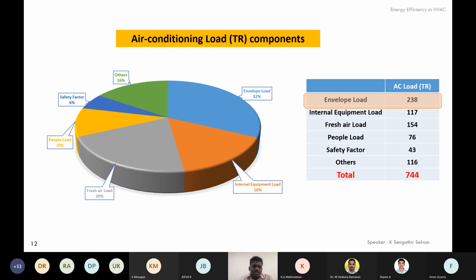Now the internal equipment actually constitutes a very small percentage compared to other loads. The computers and printers and all are very negligible in any commercial building. Of course, in a thermal plant, the heat dissipation from the electrical panels is very low, but the heat dissipation from the VFD drives and other server or other critical equipment will be a little bit high actually. But again, the people load is only 10%, and the fresh air load you can see, Chennai being a humid climate, the fresh air load is actually high. But the same fresh air load will be around 10% only if you are having this building in Hyderabad.